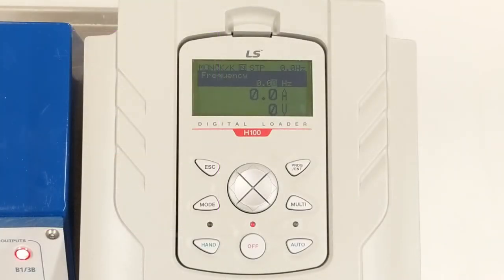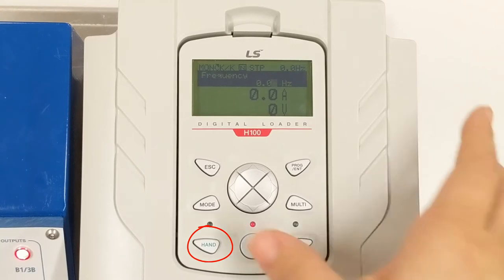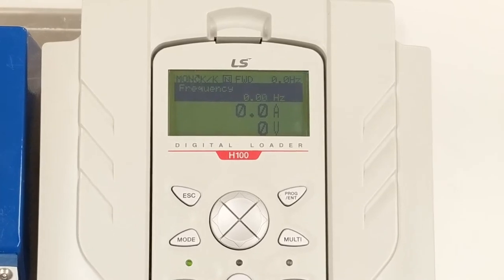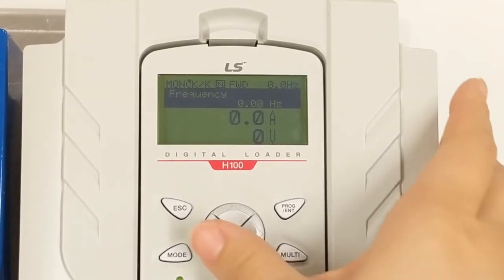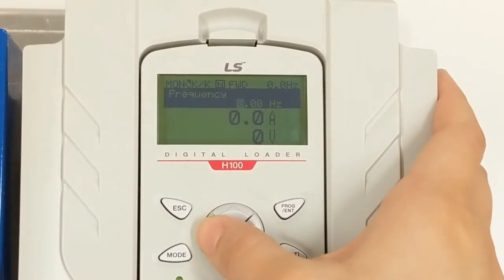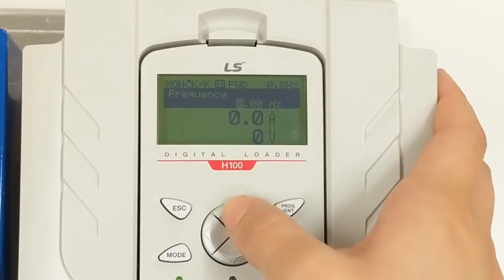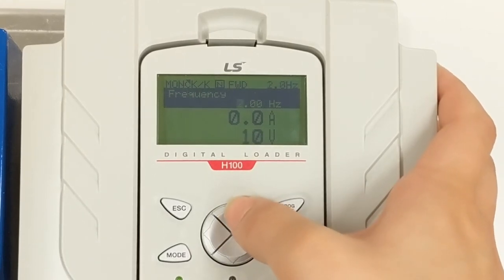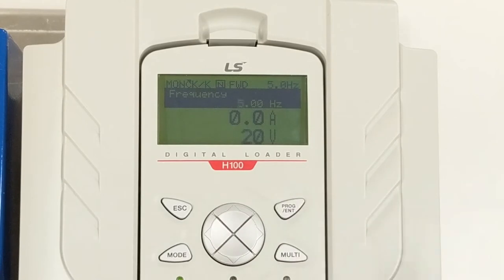Before we get into parameter changes, let's first look at how hand operation works. By pressing the hand key, you will see FWD displayed at the top of this keypad. This shows that you are in forward operation. Next, we need to give a speed reference. Let's put in 5 Hz so that we can check motor direction. Move the cursor over by pressing the left arrow until you highlight the 1's place digit, and then press the up arrow to increase the speed to 5 Hz. There's no need to press the enter key as the speed change in hand will apply immediately.